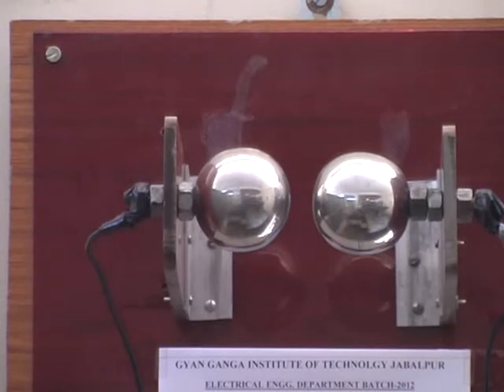The density of the air between the sphere gaps is dependent on the barometric pressure and the temperature of the ambient. As such, if we know the barometric pressure and the temperature along with the size of the sphere gaps, then depending upon the distance which is kept between the two sphere gaps, the breakdown voltage can be determined. These sphere gaps have been set for 28 kV spark over voltage. On achievement of 28 kV, a spark is there.